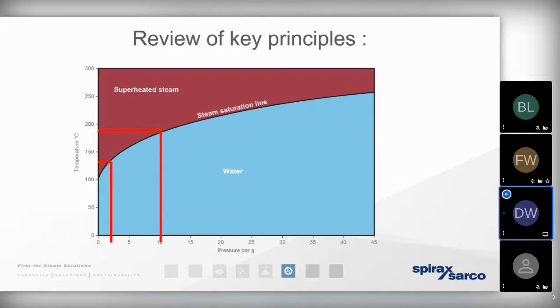And when we've reduced the pressure of the steam to satisfy the process down to 2 bar gauge or 132 degrees, the condensate will exist at the same temperature as the steam if we know the pressure. So the condensate can only exist as a liquid at that high temperature because of the pressure. So it reminds us that when steam gives up its heat energy and condenses, we've got a phase change. That latent heat energy enters the process. What's held back in the condensate is that sensible heat, but there isn't an exchange of temperature.